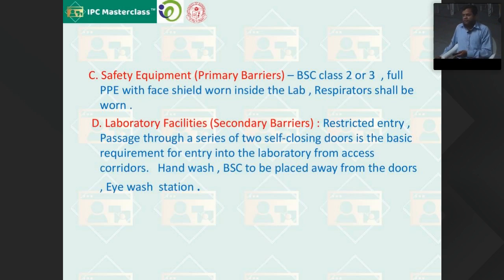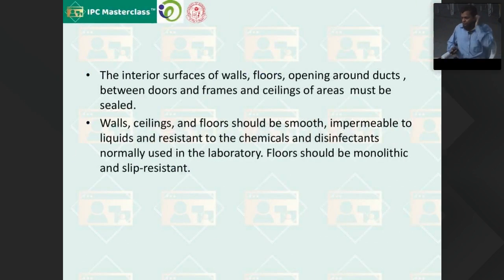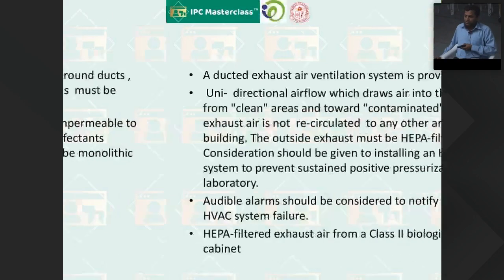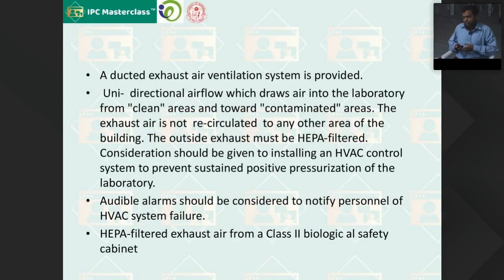Now coming to the interior surfaces of the walls and floors, they should be impervious, and the wall, ceiling and floor should be impermeable to liquids, chemicals, disinfectants. This is for the BSL3. Apart from that, a ducted exhaust air ventilation system is provided, and there should be a unidirectional flow of air from a clean part to a contaminated part, and the outside exhaust must be HEPA filtered, and consideration should be given to installing an HVAC, heating ventilation air conditioning system control, to prevent positive pressurization of the laboratory. See that there is no complication here.